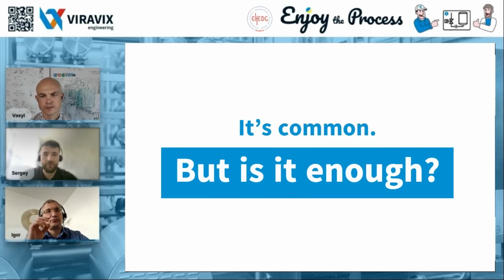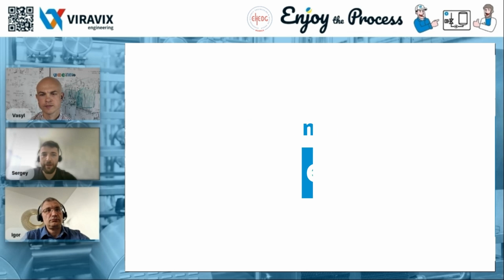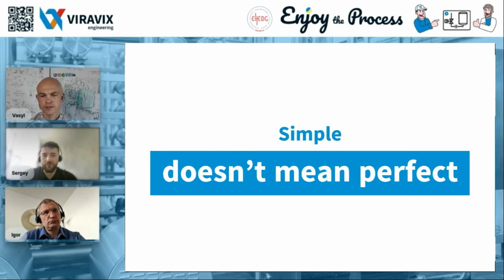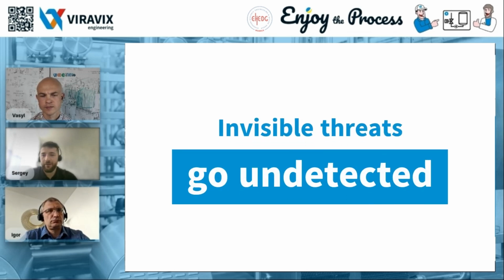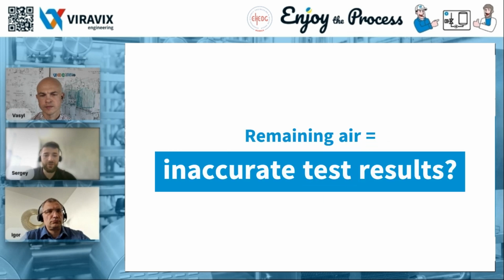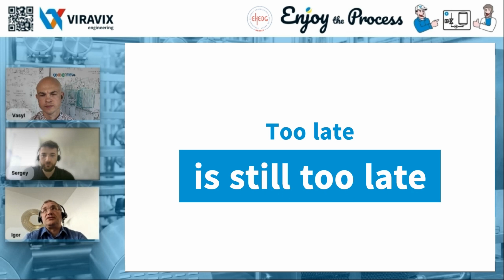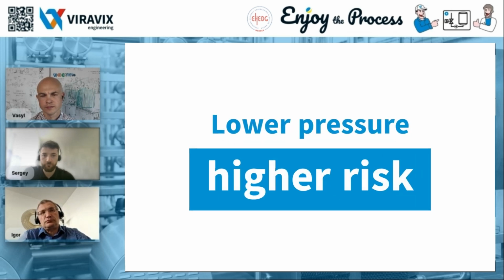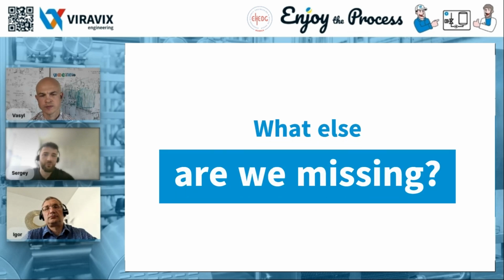It's the most accessible and one of the most commonly used methods in industrial settings. This method has quite a few limitations. It won't detect microcracks. It's nearly impossible to eliminate all the air from a heat exchanger. It can't predict or warn in advance. The lower the pressure, the lower the chance of detecting a leak. Hydraulic tests simply don't reveal microcracks.